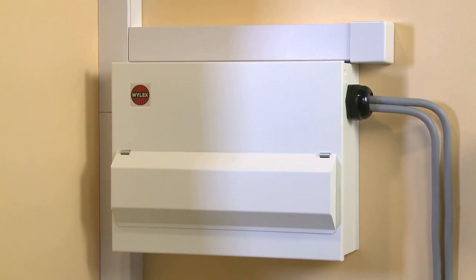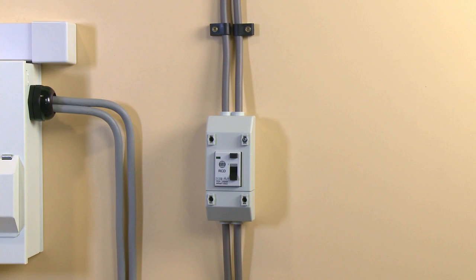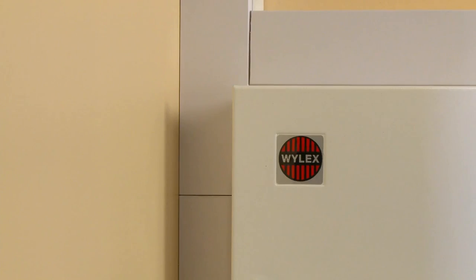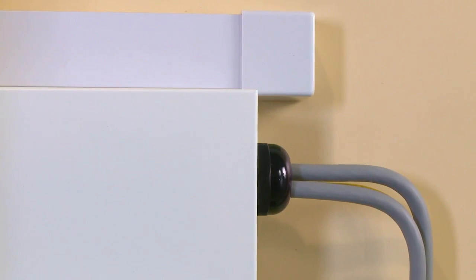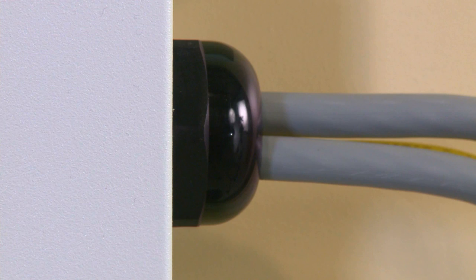In TT installations, it is also recommended that additional protection is provided by a 100 mA time-delayed S-type RCCB between the consumer unit and the supply meter to protect against the risk of faults arising from mains tails becoming loose and coming into contact with the metal enclosure. The mains tails also require mechanical protection by use of a suitable mains tails gland.